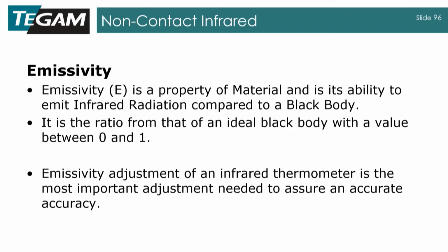If someone comes to you and says, we want to use this new infrared gun, very often if you're working at a cal lab, they'll say, what do you think of this new product we want to put in service? Something you want to look for is that the emissivity is settable. Because if you can't set the emissivity, you don't know where a person is using it. They need to set that for the surface that they're dealing with.